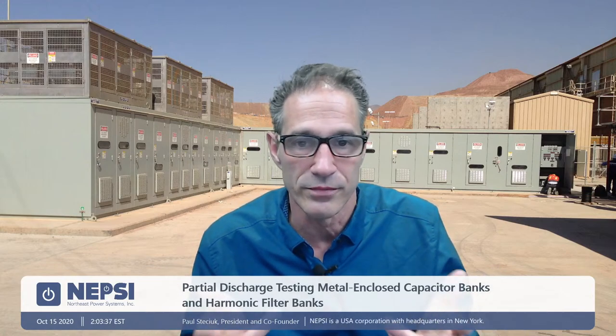We also did a Tech Talk on impulse testing, another important factory test, and impulse testing helps to also confirm the impulse rating of the equipment, that you got what you asked for. Historically, as I talked about in that presentation, it's the impulse rating of the components, the clearances, and the withstand test that were the three tests that many companies, in fact, even today, I think most companies, use only those three tests to verify that the equipment is designed for the impulse rating. So we take it one step further. We actually do the impulse test here, and we confirm that the equipment, in fact, does meet the impulse rating.